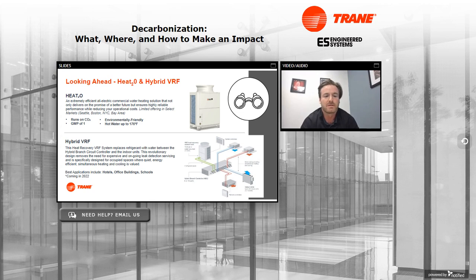Another option coming out is called hybrid VRF. It's just like a regular VRF system — you can see the parts and pieces here on the right — but it uses a standard VRF outdoor unit and transfers heat with water through a hybrid branch controller, delivering water to all your indoor units. This lowers the cost of installing water piping to your zones instead of refrigerant piping, and reduces the total amount of refrigerant in the building, which helps with the second part of decarbonization we talked about earlier. That's coming soon — 2022 is the latest launch date, so keep an eye out for that.